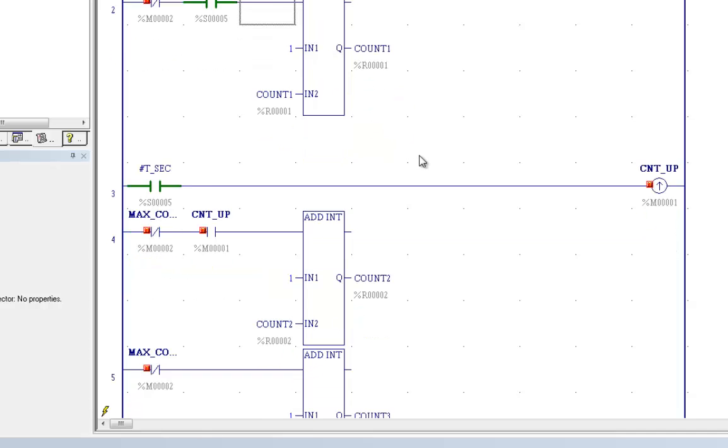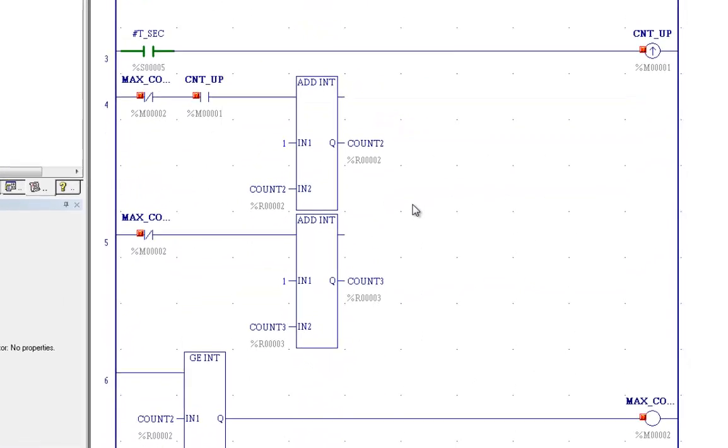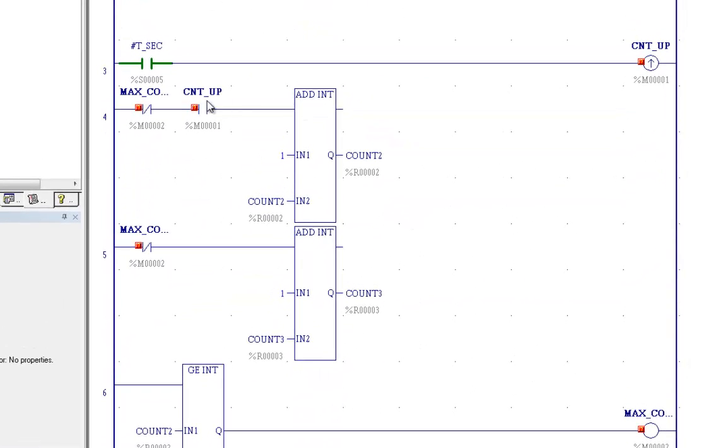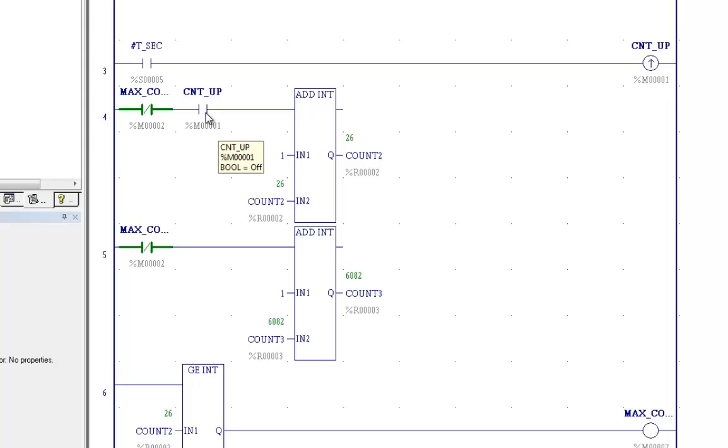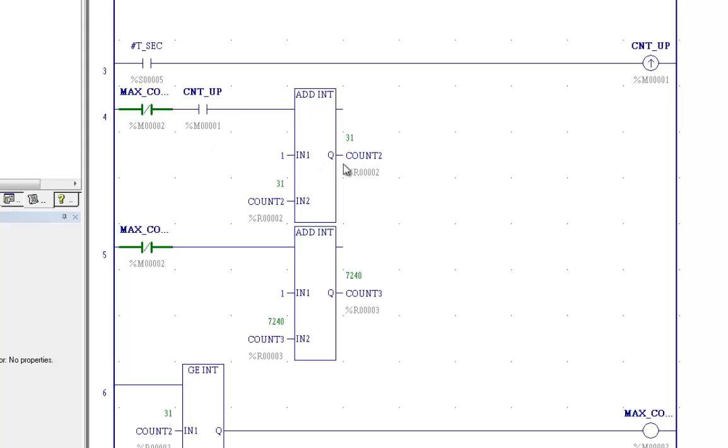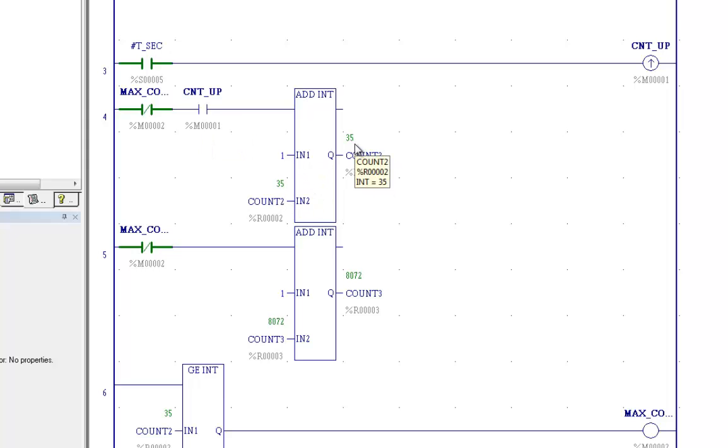If we come down over here, watch T second. You never see this light up because it's only on for one scan. You never see these contacts close because they're only on for one scan every second. But you know something is happening because you look over here and you see this count is incrementing every second. It keeps going.